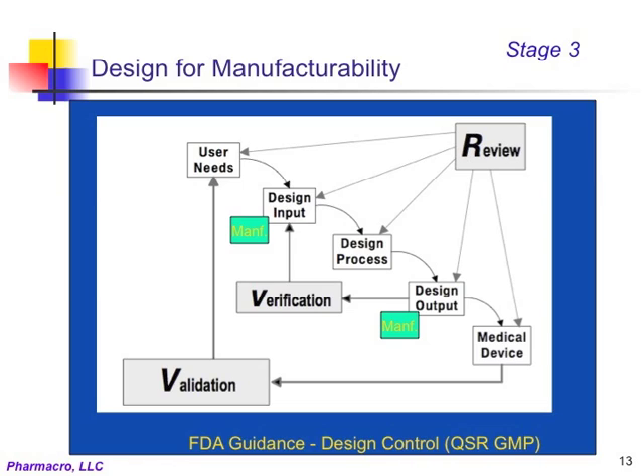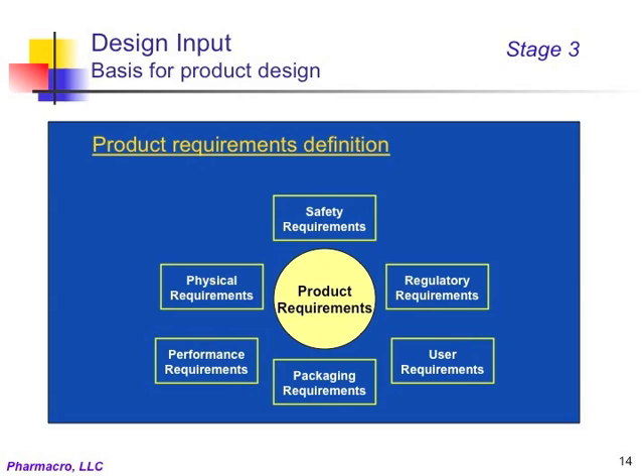Let us look at details of a typical design input document. The design input establishes the product requirements, which is the target that the development effort will be aiming for. The product requirements are as detailed as possible in order to facilitate objective and unambiguous performance evaluation of the design with respect to the requirements. The key elements of the product requirements are specific performance requirements, physical or size requirements, safety requirements, regulatory requirements, user requirements, and packaging requirements. An example may help in illustrating what these requirements might stand for.